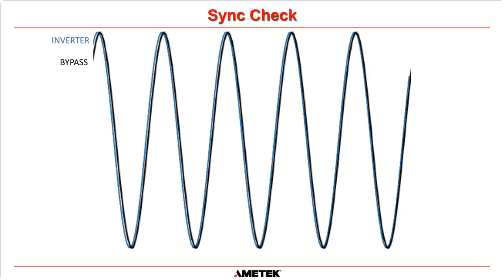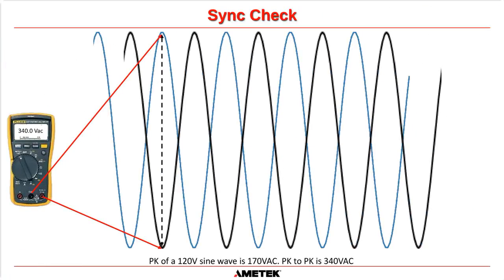So you can see on the screen here, we have two waveforms, a black waveform and a blue waveform. And in truth, I had to move them apart a little bit so you could see the two different waveforms. In a normal system, they are actually going to overlap, and it's very difficult to tell the difference because there is no phase difference between the two. But one is the inverter output and one is the bypass. The blue one's the inverter and the black one is the bypass.